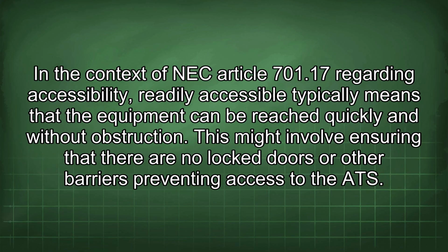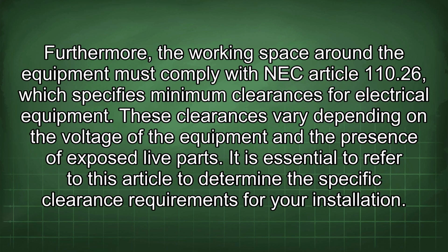In the context of NEC Article 701.17 regarding accessibility, readily accessible typically means that the equipment can be reached quickly and without obstruction. This might involve ensuring that there are no locked doors or other barriers preventing access to the ATS. Furthermore, the working space around the equipment must comply with NEC Article 110.26, which specifies minimum clearances for electrical equipment. These clearances vary depending on the voltage of the equipment and the presence of exposed live parts.